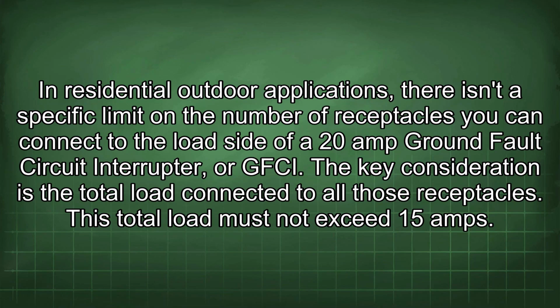In residential outdoor applications, there isn't a specific limit on the number of receptacles you can connect to the load side of a 20-amp ground fault circuit interrupter, or GFCI. The key consideration is the total load connected to all those receptacles. This total load must not exceed 15 amps.